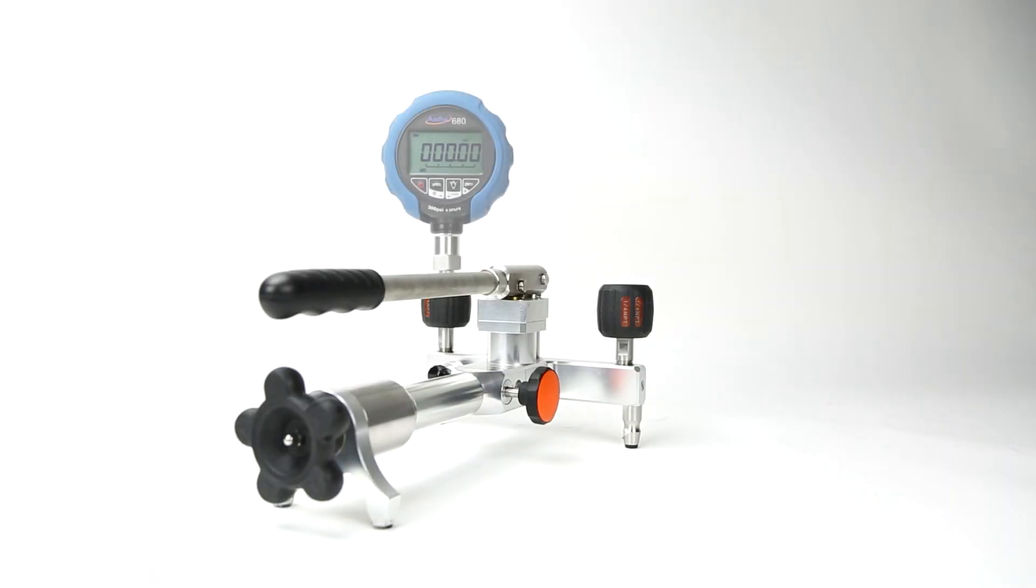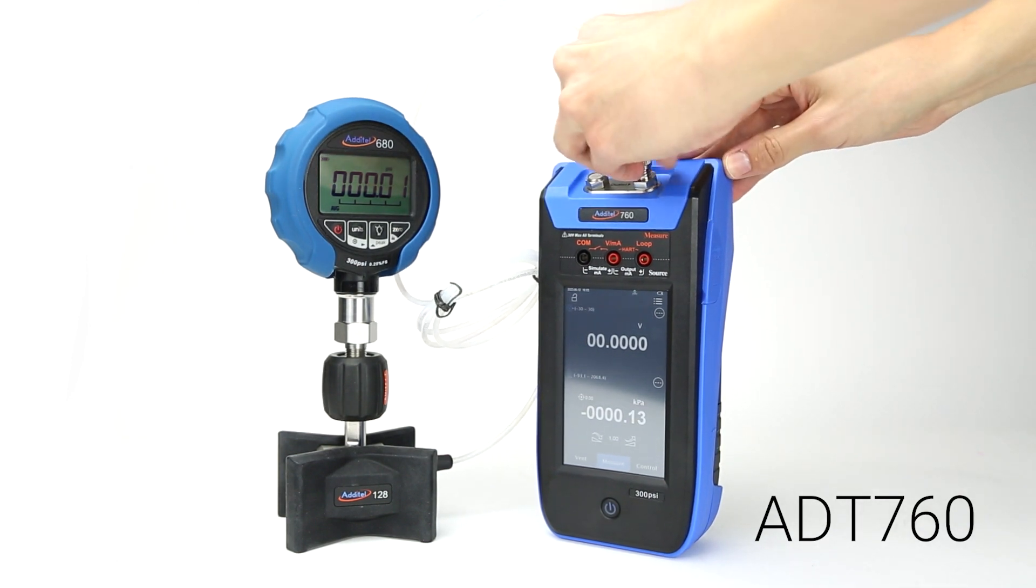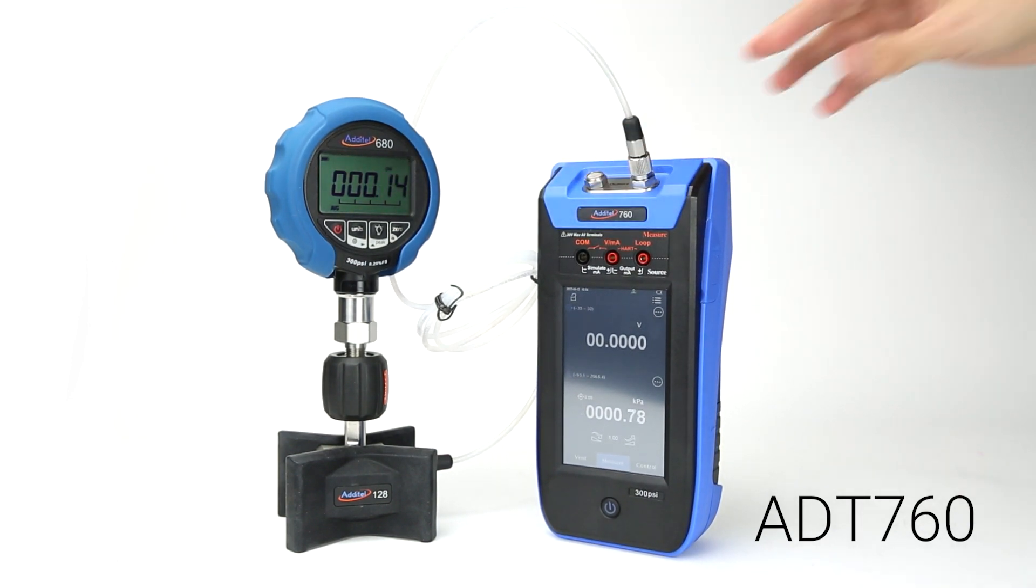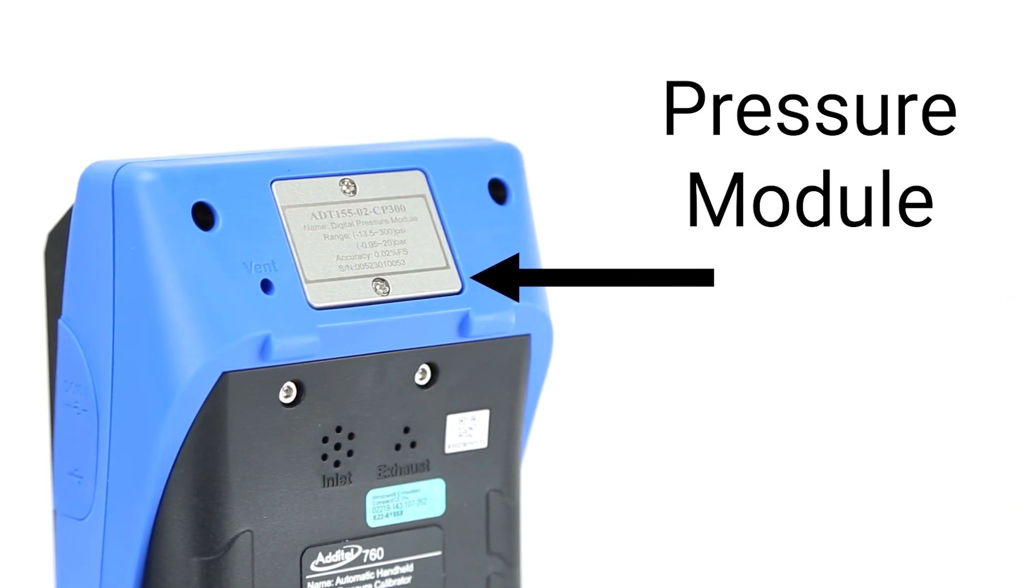For the second calibration, both the 673 calibrator and gauge under test can be connected directly to the pump. And for the third calibration, the gauge under test can be directly connected to the Additel 760 automatic calibrator, which uses a swappable pressure module on the back of the device as the pressure reference.